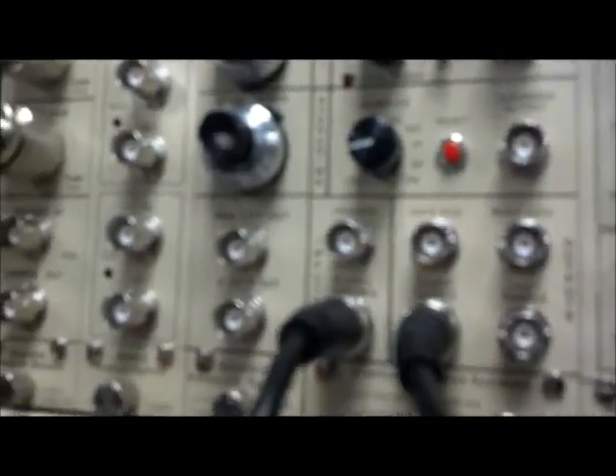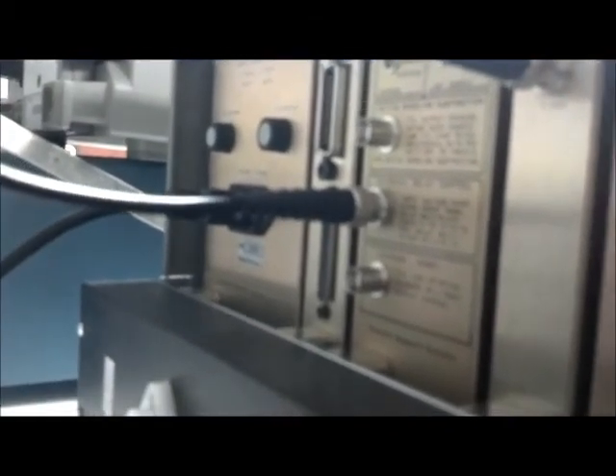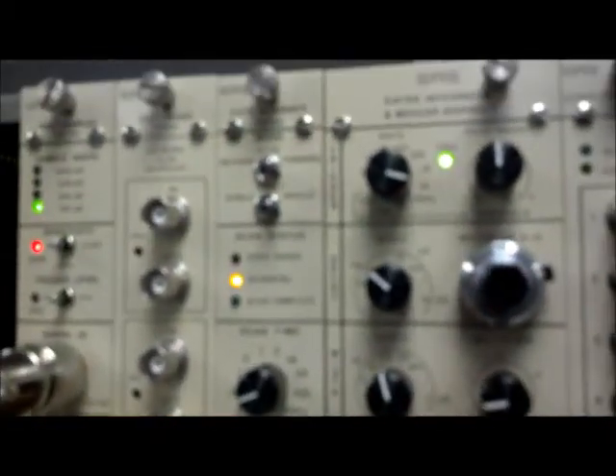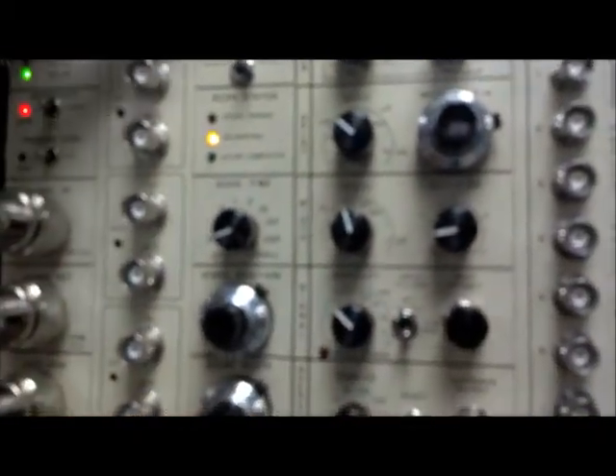In order to override the delay multiplier in the boxcar averager, we connect the control voltage. The control voltage output from the gate scanner is connected to the external delay control. This overrides the delay multiplier in the front panel, and this knob here is inactive. The scanning process is taken care of by the gate scanner now.